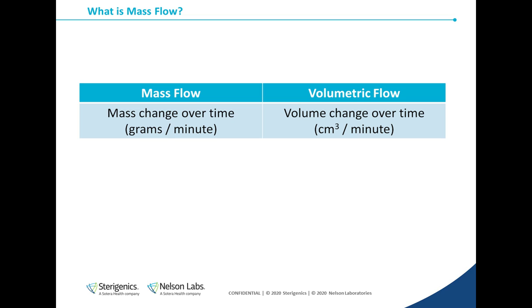What is mass flow? It's actually very similar to volumetric flow, which is more commonly understood. Volumetric flow is a volume change over time, and it's usually expressed in units like cubic centimeters per minute. Mass flow is mass change over time, and that's usually expressed in units like grams per minute. For mass extraction, the flow values are expressed in micrograms per minute because the mass extraction detector is capable of measuring to that sensitivity. So to review, the output or results for a mass extraction test are flow values in micrograms per minute. It's a flow value, but it's measuring mass to determine mass flow.